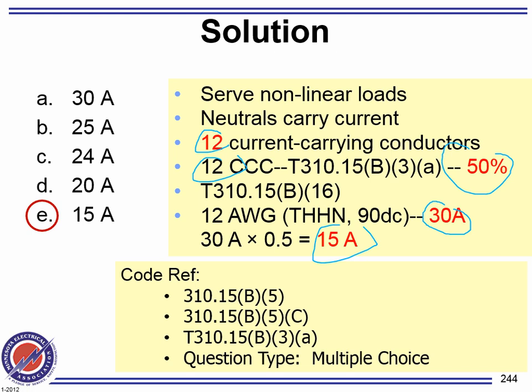You don't tell them you do not. But here's how they catch you. They say a lighting load in a commercial building that feeds electronic ballasts. That's not it. Look for electronic ballasts, electronic equipment. That's where nonlinear load comes from. You see electronic ballasts, electronic equipment, anything that has to do with electronic VFDs, soft starts, any of these, they are offenders when it comes to harmonic counter neutral.